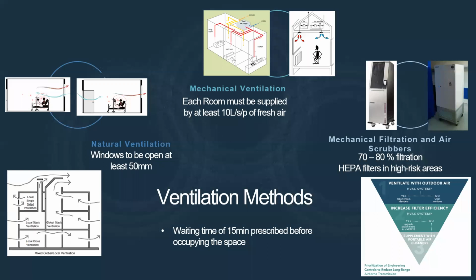Now, the reason why they use this as a gauge is it's an easy calculation to do, as a rule of thumb from a technical manager's point of view. And it also gives you the ability, when your contractors are on site, or if you do have your technical facilities manager with testing equipment, to actually calculate this if you really want to go into the finite detail of what each room does provide you with. You can create this flow rate of 10 liters per second per person in 2 different ways. The one is by means of fresh air discharge. So you discharge fresh air into that particular room, and that is your flow rate for fresh air supplement. Or you could do it for extraction purposes. So you extract 10 liters a second in that room, and your makeup air either gets supplemented from a passage or from a fresh air system that's outside that particular room.